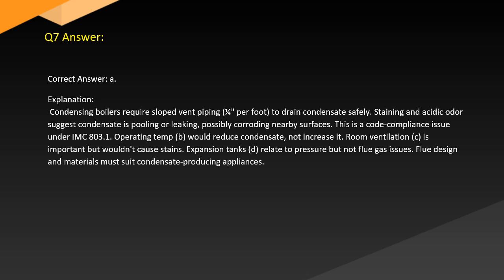Answer. Correct answer: A. Explanation. Condensing boilers require sloped vent piping, 1/4 inch per foot, to drain condensate safely. Staining and acidic odor suggest condensate is pooling or leaking, possibly corroding nearby surfaces. This is a code compliance issue under IMC 803.1. Operating temperature (B) would reduce condensate, not increase it. Room ventilation (C) is important but wouldn't cause stains. Expansion tanks (D) relate to pressure but not flue gas issues. Flue design and materials must suit condensate-producing appliances.